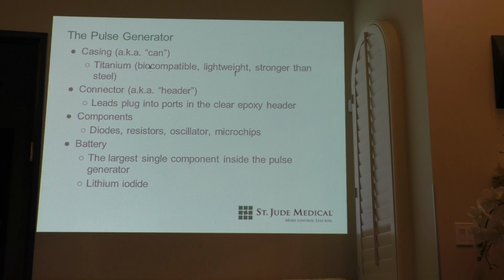You've got the can, right? The hard metal part is made of titanium. The header is the acrylic part where we can see through. That's obviously important because you want to be able to make sure that the connection is good and be able to visualize any problems. And then inside there's a computer network system that has all sorts of very tiny parts on it, including a motion sensor and a capacitor to be able to increase the voltage from the battery voltage. We have to deliver higher voltages to the patient.